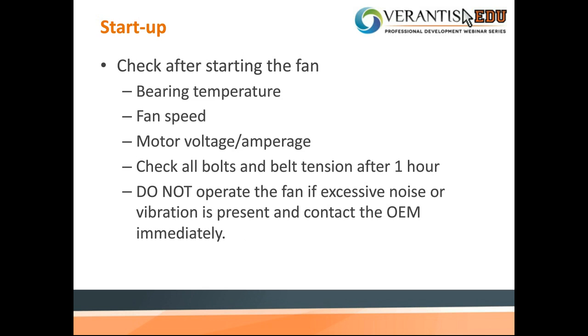So check after the fan has been started. All of these are typically checked in the field, but still check to see if the motor bearing temperature is within range and hasn't been elevated. Check the fan speed. Check motor voltage, check amperage, check all the bolts and belt tension after 1 hour. Do not operate the fan if excessive noise or vibration is present, and contact your OEM immediately. If a fan leaves the shop, they want to make sure it's good in your field, and definitely contact the OEM.